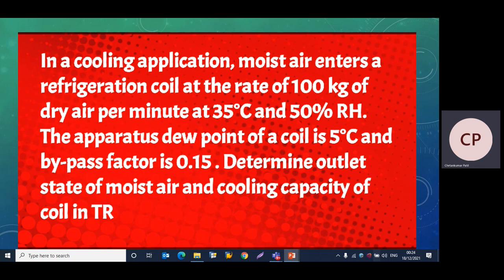The apparatus dew point of the coil is 5°C and the bypass factor is 0.15. We need to determine the outlet state of moist air and the cooling capacity of the coil in tons of refrigeration.